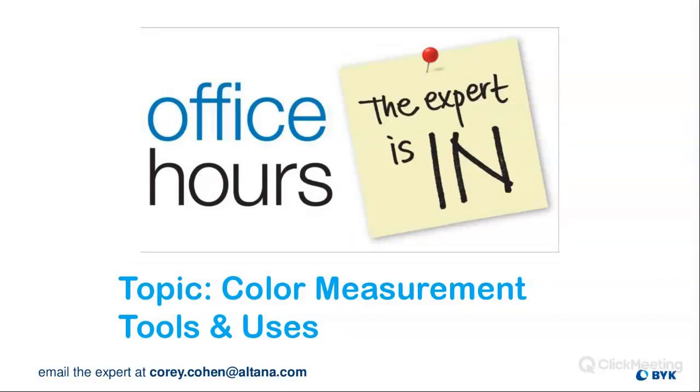You can also just take a sample measurement. Make sure you're in the right settings, of course. Most of these, the nominal values are given under D65 10-degree observer. So make sure your settings are correct and take an absolute reading of the green checking standard, and you can see whether it's in calibration or not.